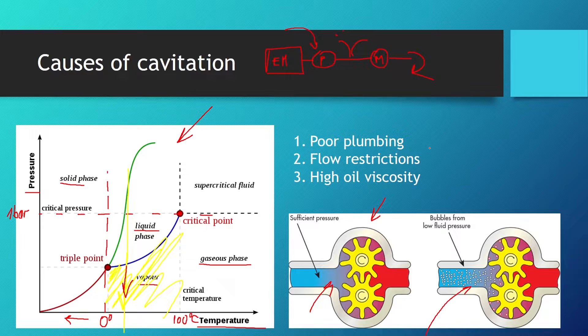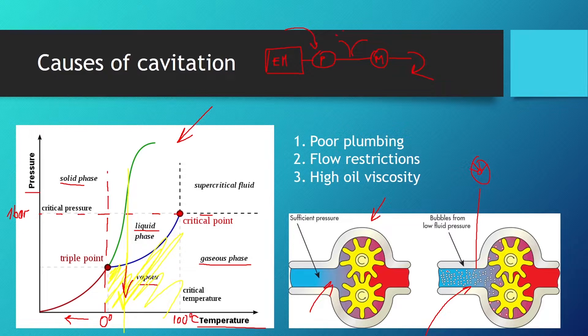One of the main factors that contribute to cavitation is poor plumbing, flow restrictions, and high oil viscosity. There are usually pressure gauges placed on the inlet of the pump so we don't get into vacuum territory, because if the pressure is really low on the inlet side we have the formation of vapor bubbles which later burst and damage our components.